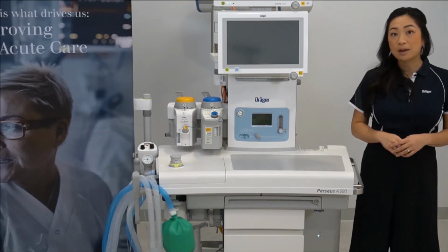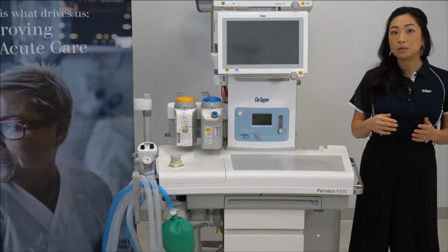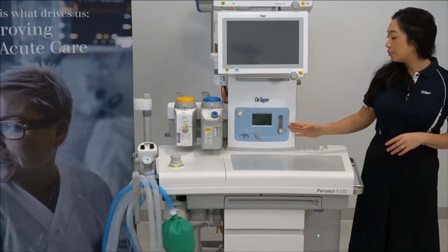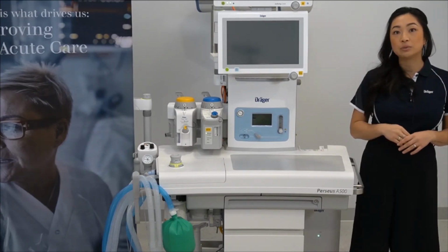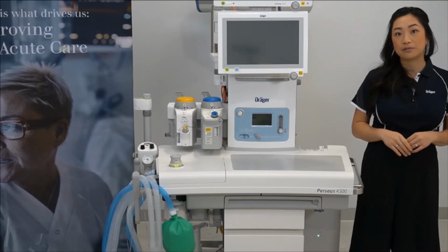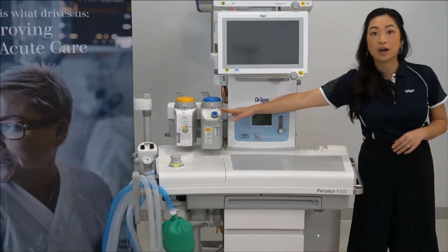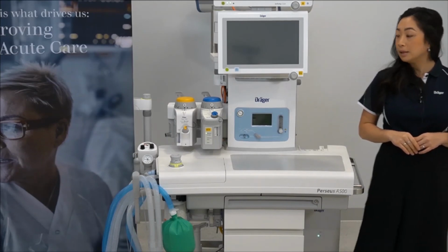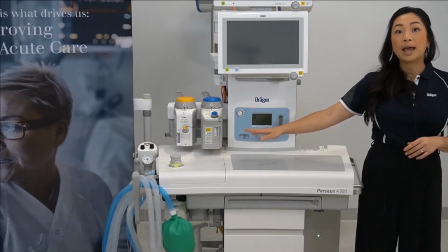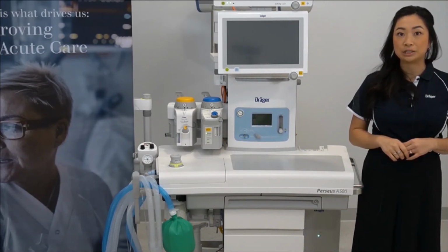Just keep in mind for users that were flowing low or minimal flow anaesthesia that moving over to your additional oxygen will deliver a significantly higher flow. Therefore, please verify your vaporizer settings. Check your APL valve and start manually ventilating the patient.